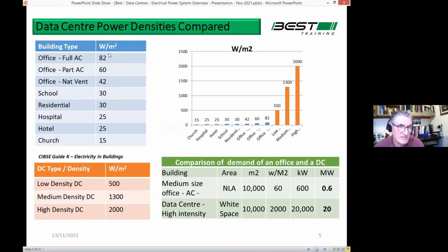And you can see their power density is quoted usually in watts per square meter. The square meters obviously refers to the net lettable space on a school, the classroom space. It doesn't include plant room space or anything like that. So it's the net lettable space of the building. So you can see for a fully air-conditioned office building, it's quoted around 82.